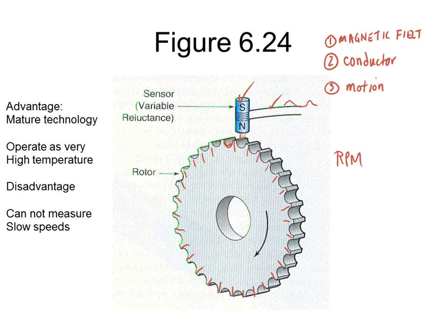Because we've got multiple teeth per revolution. If we only had one little magnet per revolution, that's all we'd sense, just that one magnet. Here we can sense all the teeth on that gear. Basically all we need is a gear, a metal gear, and the whole gear itself doesn't have to be metal, all the rest could be plastic as long as the teeth themselves are metal.